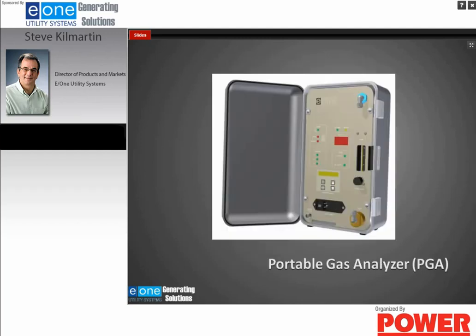This is a picture of a portable gas analyzer, which again I recommend be used during the purging of the generator. This is for temporary installation. It is not meant to be installed permanently. It is also meant to be used in an area that is well ventilated, where you don't have a chance for hydrogen buildup.